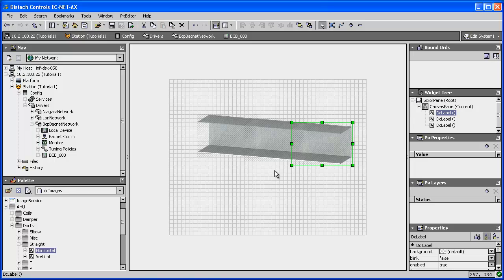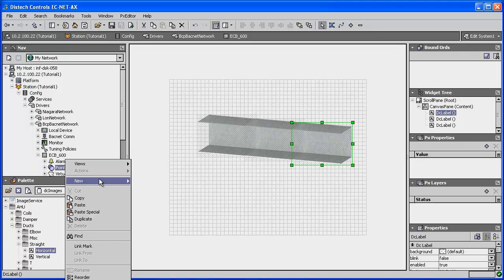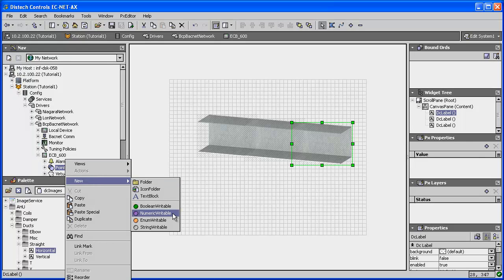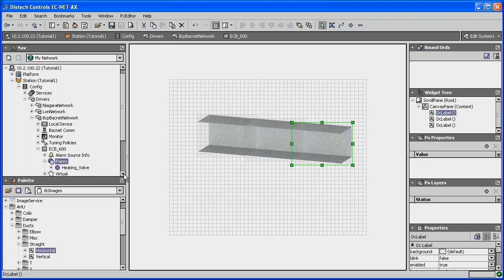Now to further enhance my graphic, I can add extra components such as a vertical heating coil. Unlike the ducts I just added, the coil will be an animated graphic that depends on a certain value. I will start by adding a numeric writable control point because if it isn't associated to a point, it has no value and therefore no image will be displayed. I will right-click on the device's points folder, then select New and select the numeric writable control point. I will rename my control point to Heating Valve. The point then appears under the Points folder.